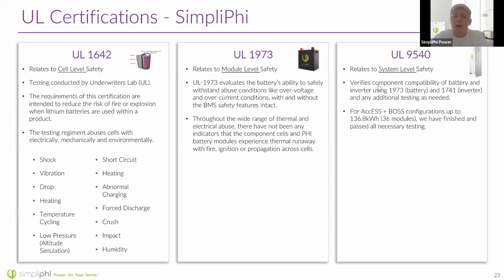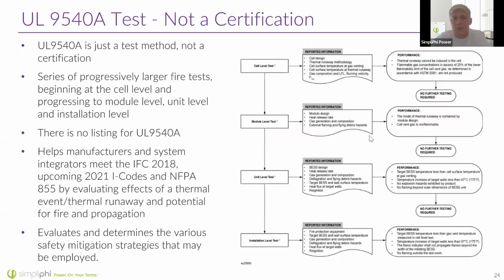And UL 9540, this is a system level safety test. It's going to verify not only that the battery is safe, but that the entire system, meaning battery and inverter charger, are going to work together safely. For ACCESS and BOSS configurations, we have finished all necessary testing, so we do have UL 9540 completed and ready to go. This is something a lot of jurisdictions are asking detailed questions about, wanting to see our 9540 certification. And a lot of them are wanting to see our 9540A report, which is something that we have.